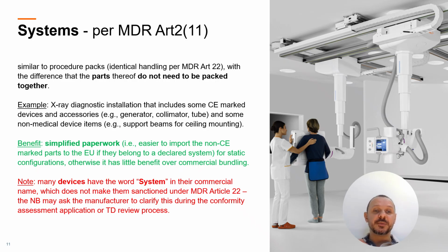Similar to the procedure pack, the benefits are simplified paperwork. It is easier to import the non-CE mark parts to the EU if they belong to a declared system, for static configurations, otherwise it has little benefit over the commercial bundling. It should be noted that some devices have the word system in their commercial name, which does not make them sanctioned under the MDR Article 22. The notified body may ask the manufacturer to clarify this during the conformity assessment application or during the TD review process.